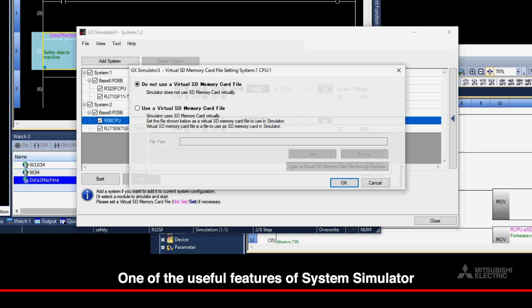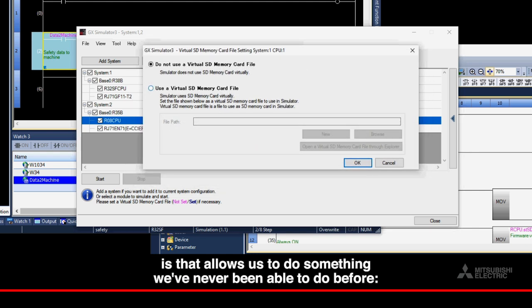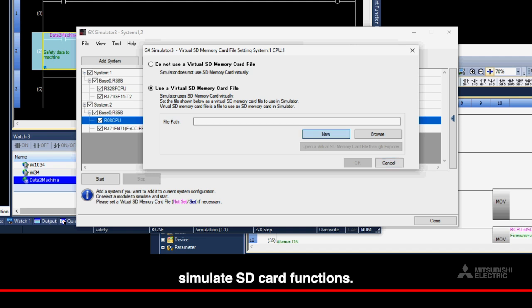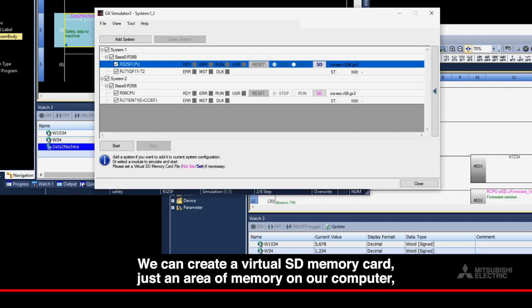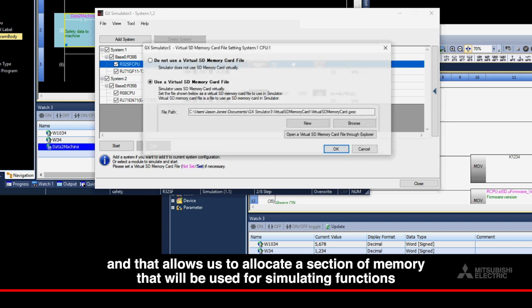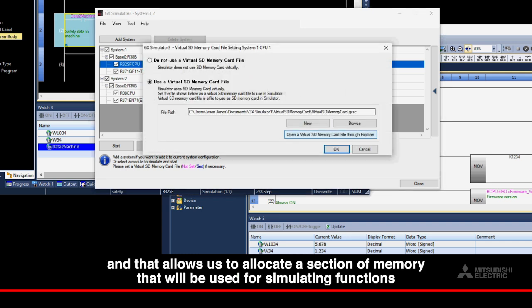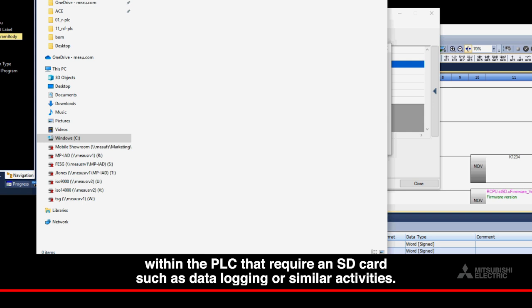One of the useful features of System Simulator is that it allows us to do something we've never been able to do before: simulate SD card functions. We can create a virtual SD memory card, just an area of memory on our computer, and that allows us to allocate a section of memory that will be used for simulating functions within the PLC that require an SD card, such as data logging or similar activities.